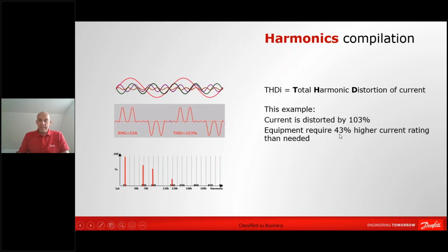In this case, it's 43% higher. It's the 55 amps; it's the square root sum you calculate it by, so that's how you get to the 43% higher RMS current. So basically, when we're talking about harmonic currents, the problem is that you need to size everything in front of the frequency converter for a higher current. That means that the cables need to be able to take the extra current, the switchgear needs to be sized for the higher current, and the transformer needs to be sized for the higher current. And that basically means that you need to oversize your components when you have a lot of current distortion on your supply network.